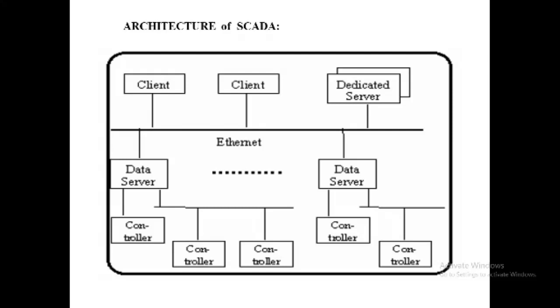Then access to the device. The data server polls the controller at a user-defined polling rate. The polling rate may be different for different parameters. The controller passes the requested parameter to the data server. Then time stamping of the process parameter is typically performed in the controller, and this timestamp is taken over by the data server. If the controller and communication protocol used support unsolicited data transfer, then the product will support this too.